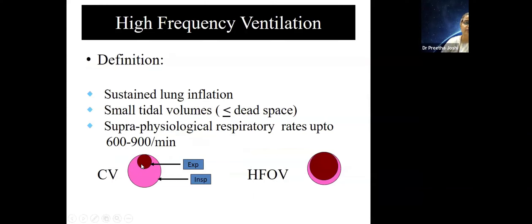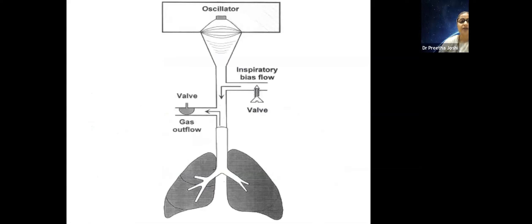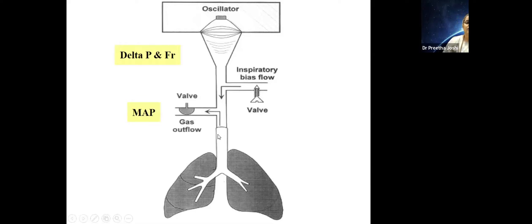During conventional ventilation there is inspiration followed by a big change in lung volume during expiration due to pressure. In high-frequency ventilation, pressure is sustained, so there is much less shear stress and strain injury. In the graphical model, a diaphragm oscillates with an inspiratory bias flow coming in, and a gas outflow valve regulates how much pressure is maintained inside the lung. The MAP is maintained by this mechanism, and the oscillator delta P and frequency come from the piston.